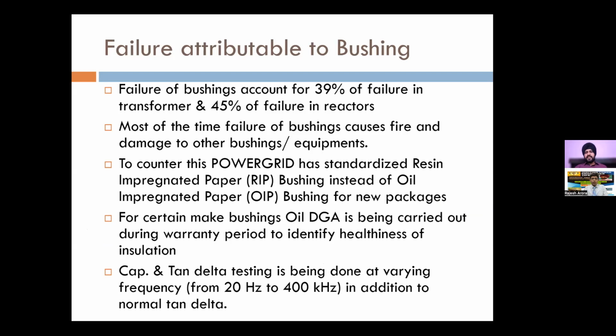Now we have standardized RIP bushing from 400 kV up to 145 kV. Even for 52 kV, it is optional. So sometimes we are taking RIP bushing, sometimes we are taking OIP bushing as per the requirement. And regular oil DGA for OIP bushings, the older OIP bushing, we are carrying out within the warranty period and even after the warranty period if there is any issue. So this ensures that any initial incipient fault in the bushing can be captured.